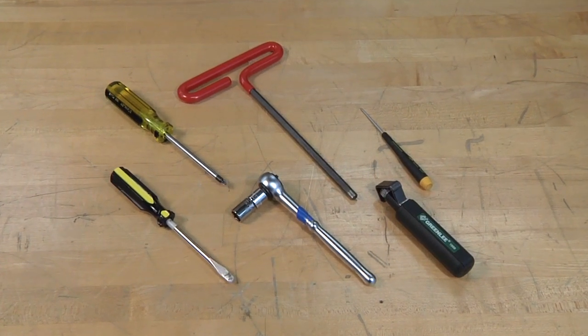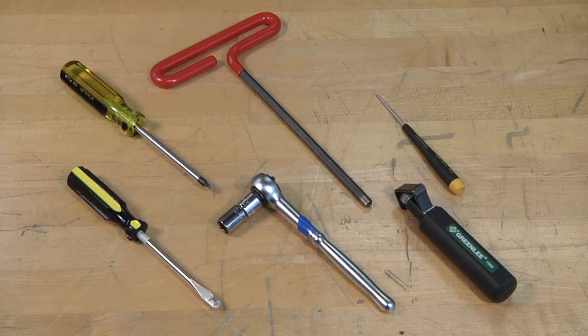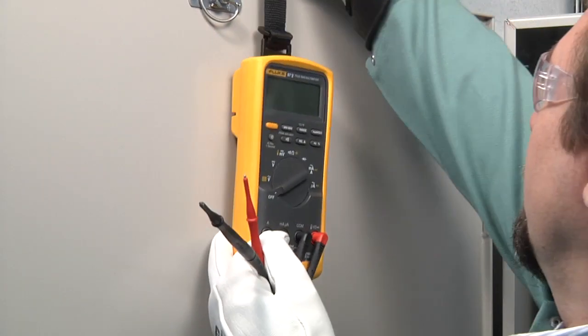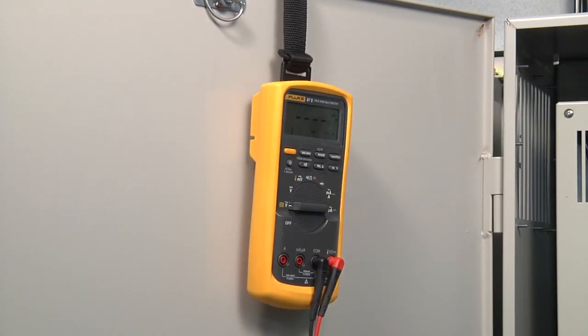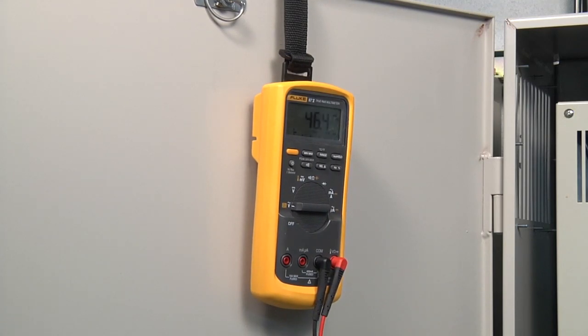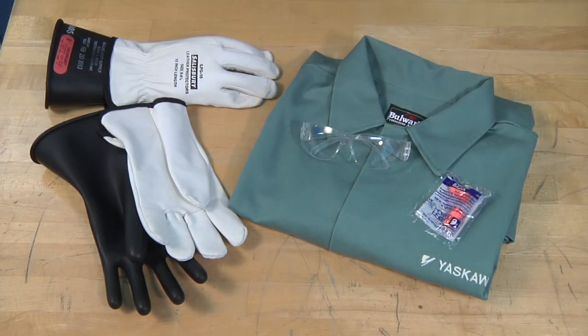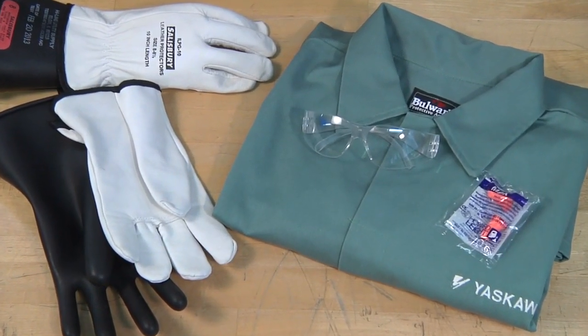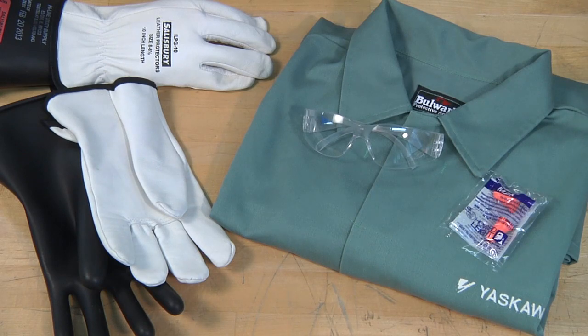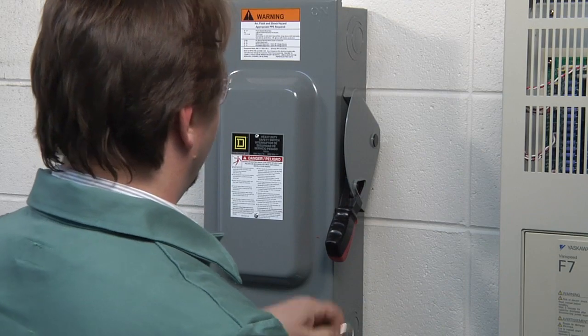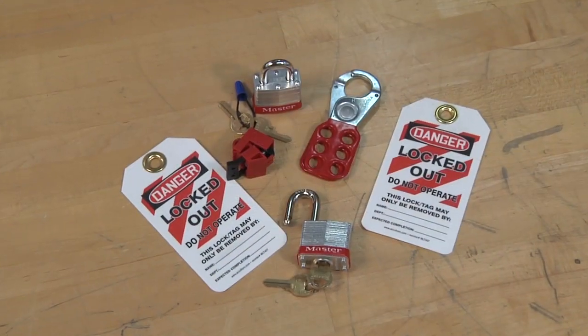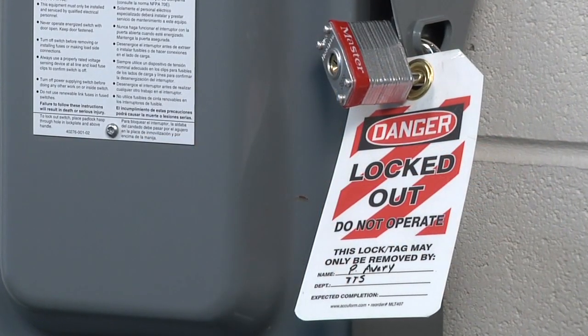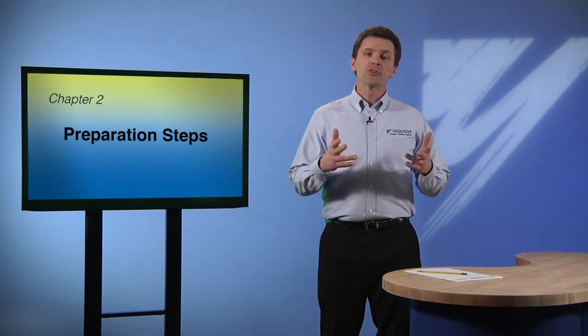If you start the setup process by gathering together all the tools you'll need, things will go smoother down the line. Be sure you have a set of standard flathead screwdrivers, both a small one and a large, plus a pair of wire strippers and a T-bar Allen wrench. You'll also need a digital multimeter, one that is able to accommodate voltage levels over 1000 volts DC and is rated for a minimum of Cat 3 measurements, but preferably Cat 4. Safety equipment is essential. We're dealing with high-power circuitry here, so you'll need a set of gloves, safety glasses, a cotton coat, and hearing protection. Lockout-tagout for a process like this is absolutely required, so you'll need lockout-tagout equipment. Last but not least, make sure you have a paper and pencil to write down some important information about your system.